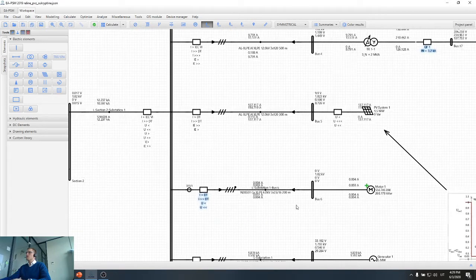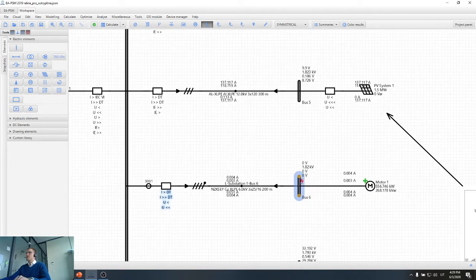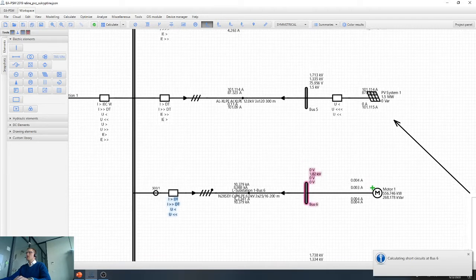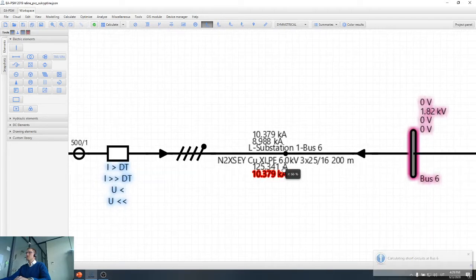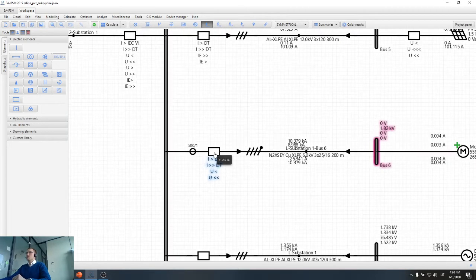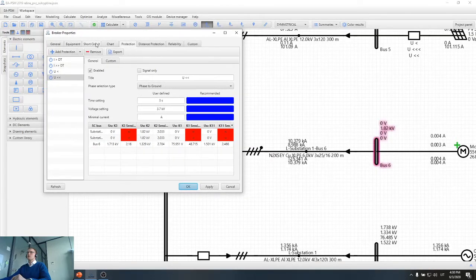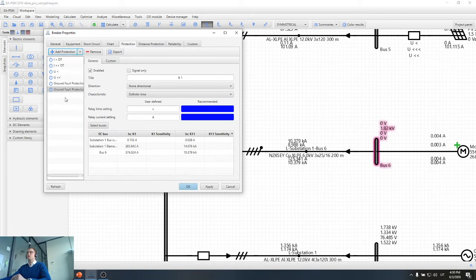So let's check what the zero sequence current will be if I have a short circuit here. You can see it's about the same size, 125 amps. So when I set my earth fault protection devices, let's add the earth fault protection devices. I will also add 2 stages. First of all, we need to set the time, let's say, for the first stage. The first stage name will be earth current more.